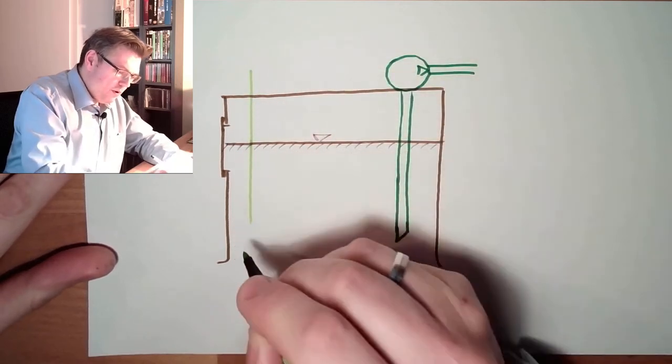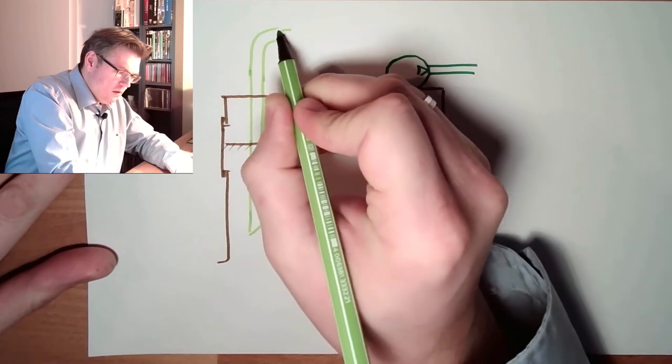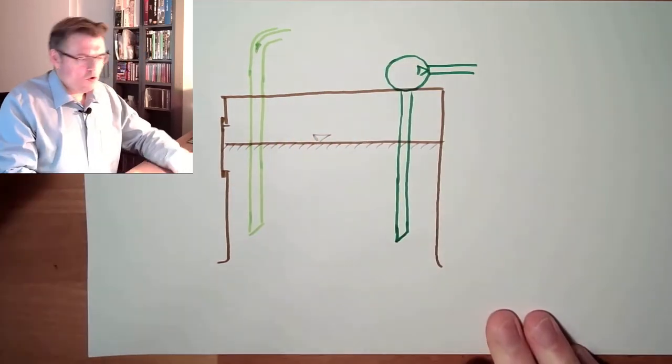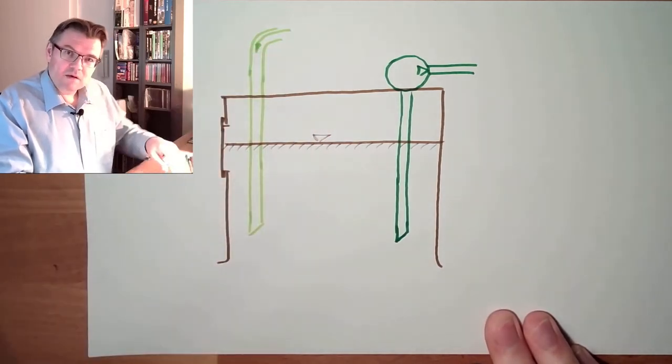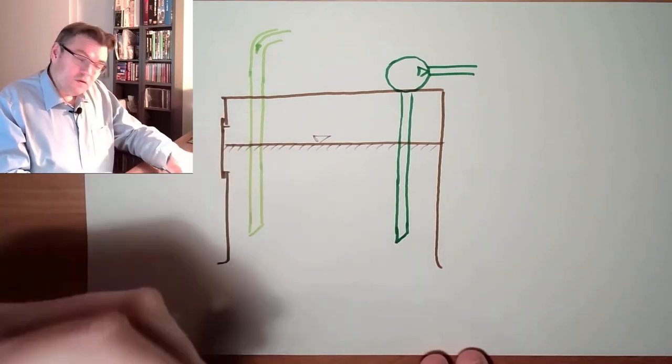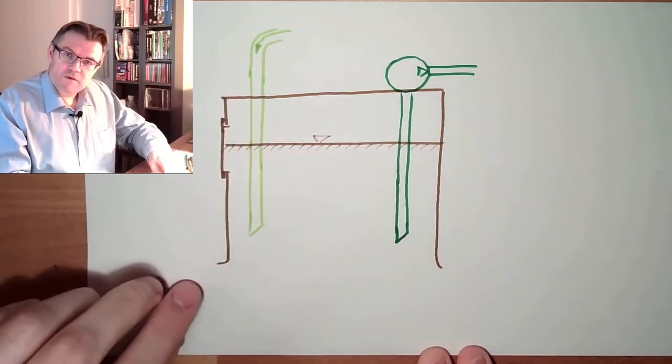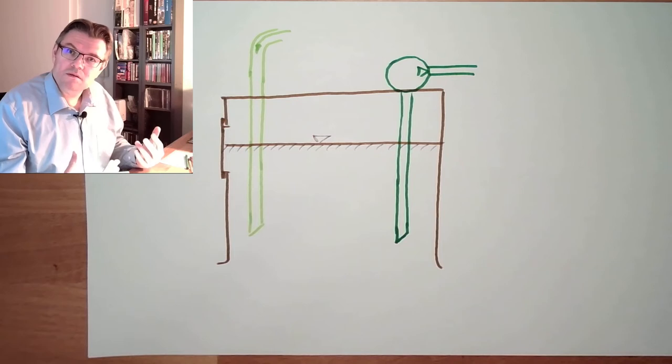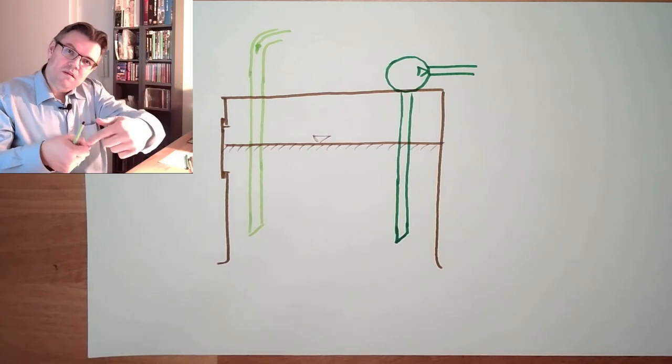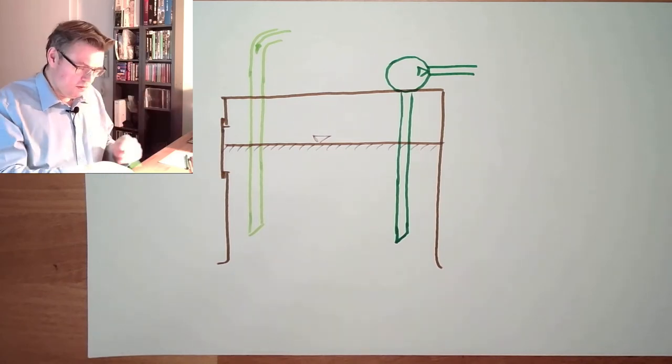And then in another place we have the return line. The return line will also go below the surface, for sure, also cut. This is the return line where the oil is coming back. Why do we not spill it? Because we don't want to get in air or disturb. We don't want to get foam, so we simply pull all those tubes below the surface so it's not foamy there. Same reason why from the tap at the beer, not too much foam, same reason here.